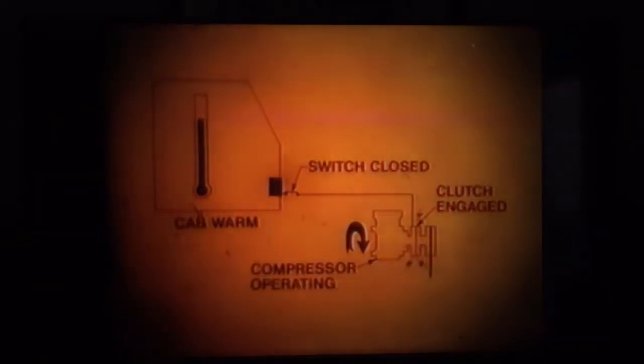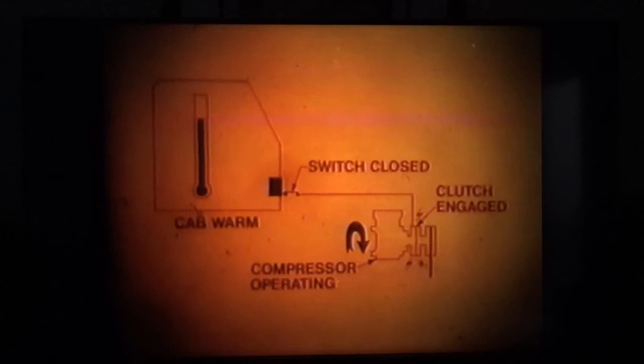When the temperature rises above the setting of the control, the electromagnetic clutch is energized and the compressor begins pumping refrigerant through the system. The refrigerant enters the compressor in a low-pressure vapor state. The compressor compresses, superheats, and propels the refrigerant vapor through the hoses to the condenser. The refrigerant vapor, now under high pressure, travels through the condenser coils, where the air flowing over the condenser removes the heat from the refrigerant and causes the vapor to condense into a liquid.